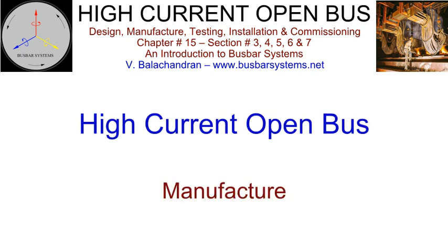Manufacture. Major components of open busbar for high current DC applications are limited to conductors, spacer plates, and laminates. These together form a significant cost of the busbars. Fixings and insulators are bought-out components. Most of the assembly of the components takes place at the site. However, certain sub-assemblies are manufactured at works, which can be transported and assembled at the site. Sizing the busbars to correct dimensions, machining and drilling for end preparation and welding form the major fabrication activity.